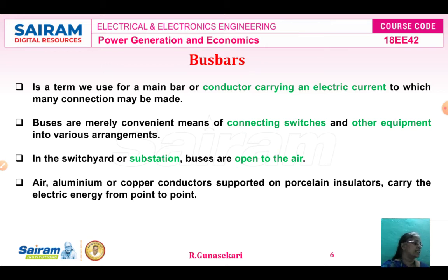The size of the bus bar is important in determining the maximum amount of current that can be safely carried. The bus bar should be able to carry the expected maximum load current without exceeding the temperature limit. The capacity of the bus should be checked for maximum temperature under short circuit conditions.